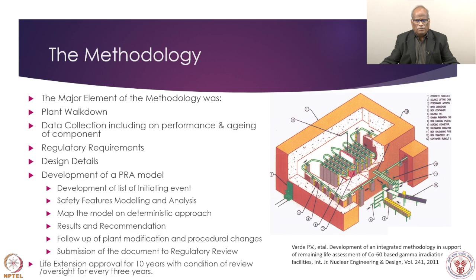This is a simple figure showing how products are irradiated. There is a chamber so that radiation does not come out. There is a source, and around the source there is a conveyor belt on which the product enters, goes around the source location, and finally comes out. It is a simple and elegant design, but aging study is always complex because it can become expensive if you cannot determine which components to replace and which not to replace. The methodology adopted here is based on a paper published in Nuclear Engineering and Design.